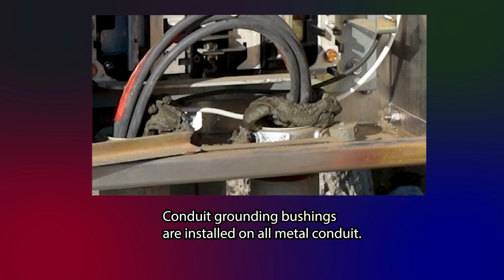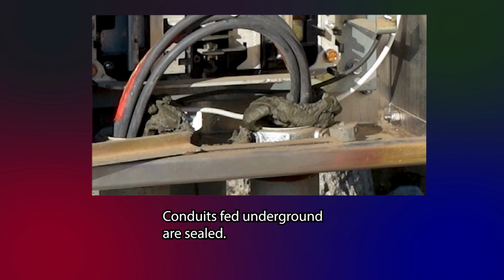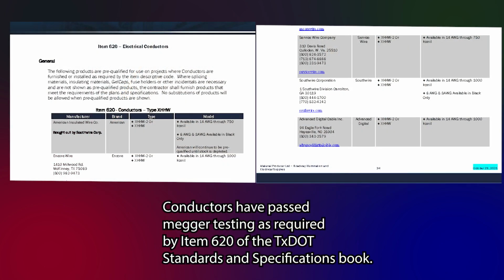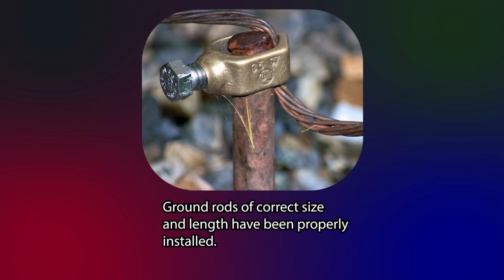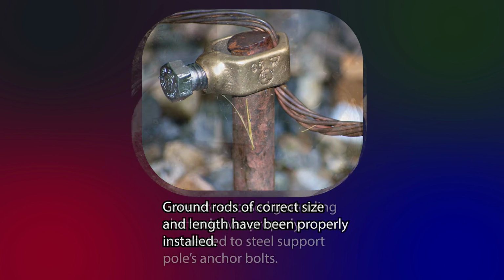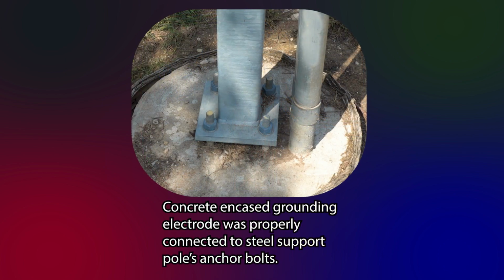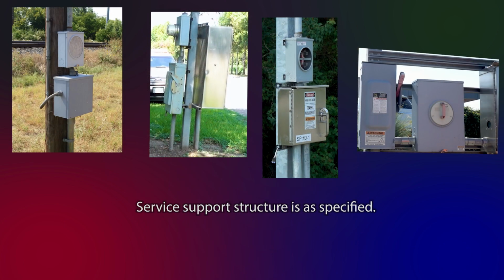Conduit grounding bushings are installed on all metal conduit. Conduits fed from underground are sealed. Conductors have passed Megger testing as required by Item 620 of the TxDOT Standards and Specifications book. Ground rods of correct size and length have been properly installed. Concrete encased grounding electrode was properly connected to steel support poles anchor bolts. Service support structure is as specified. This completes our review of the inspection of the Type D electrical service.